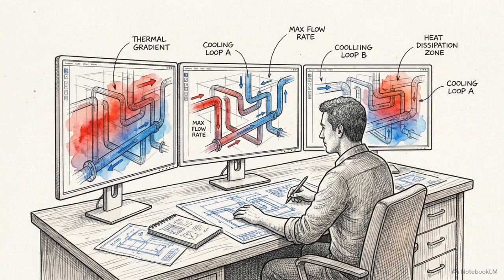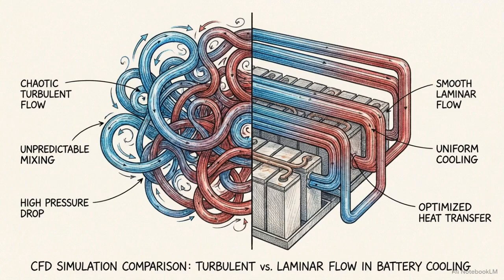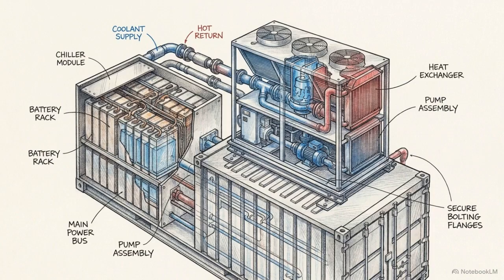To prevent this, thermal engineers use computational fluid dynamics, or CFD. By simulating fluid velocities and pressure drops mathematically, they resolve uneven flow distributions in software long before the first steel pipe is ever welded. Millions of dollars of premium industrial hardware, compressors, and battery cells are entirely useless without rigorously validated flow dynamics and intelligent control logic guiding them.